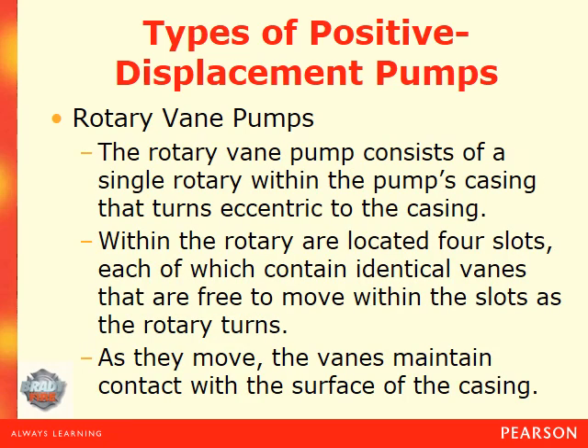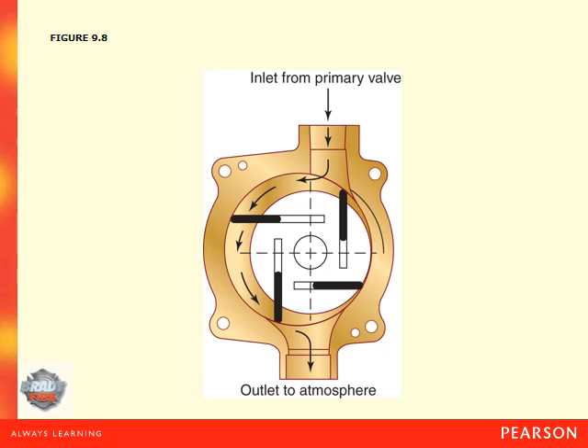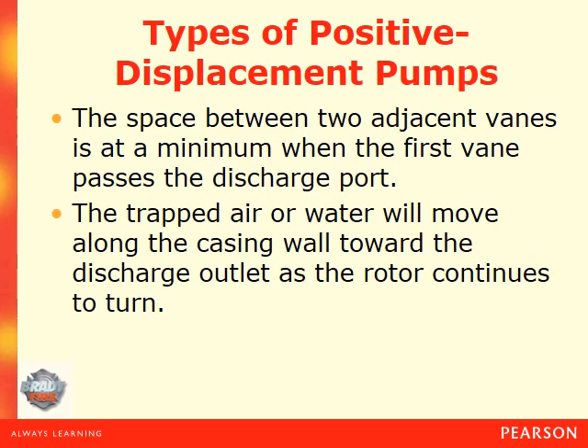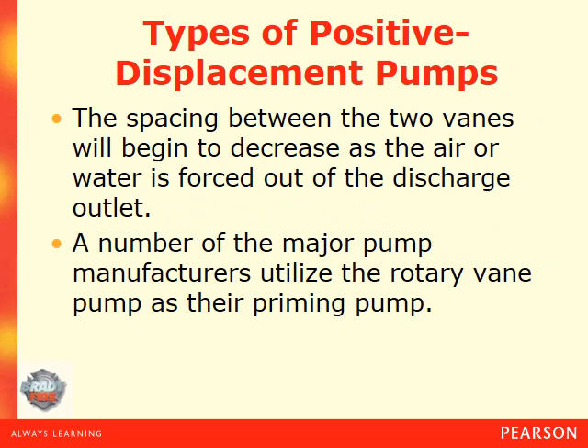Rotary vane pumps consist of a single rotor within the pump casing that turns eccentric to the casing. The rotor has four slots, each containing identical vanes that are free to move within the slots as the rotor turns. As they move, the vane maintains contact with the surface of the casing — it comes in, spins around, and is forced out of the pump. The space between two adjacent vanes is at a minimum when the first vane passes the discharge port. The trapped air or water moves along the casing wall toward the discharge outlet as the rotor continues to turn, and the space between the vanes decreases as the air or water is forced out. A number of major pump manufacturers utilize the rotary vane pump as their priming pump.